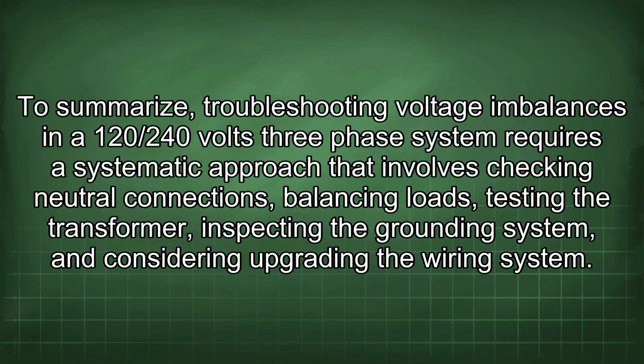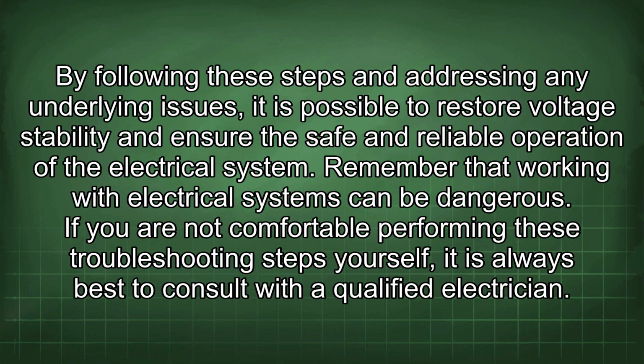To summarize, troubleshooting voltage imbalances in a 120/240 volts three-phase system requires a systematic approach that involves checking neutral connections, balancing loads, testing the transformer, inspecting the grounding system, and considering upgrading the wiring system. By following these steps and addressing any underlying issues, it is possible to restore voltage stability and ensure the safe and reliable operation of the electrical system.